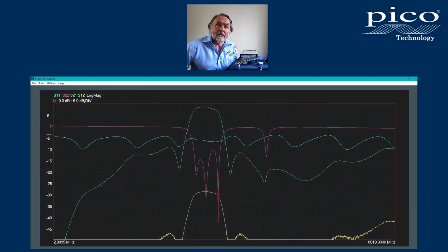Now, instead of 4 S parameters in 4 display channels, we might now choose to view all 4 S parameters on a single plot. Each display channel can now support up to 4 live traces, as seen here. An obvious benefit being that the display alignment between each of the 4 S parameters for our device under test is now much more clear.